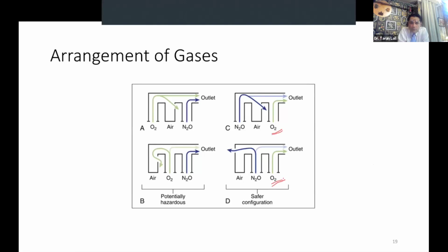Why is it important? Let's assume that oxygen is upstream, either at position number 1 or number 2, and suppose there is a leak. Then there is a chance that only oxygen is leaking, and the patient will get a hypoxic mixture. Whereas if oxygen is the last gas that is added, then if there is any leak beyond the point where oxygen is added, the entire mixture will leak. Only oxygen will not leak.